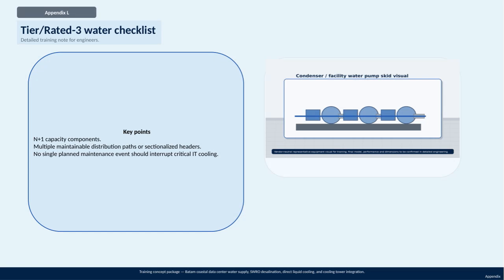Here in Appendix L, we focus on the Tier 3 water checklist, which serves as a detailed training guide for engineers. This training concept package is specifically designed around the Batam Coastal Data Center's water supply system. It covers crucial elements such as SWRO desalination, direct liquid cooling, and the integration of cooling towers. The key points to understand include the use of N+1 capacity components, ensuring redundancy and reliability. Additionally, there should be multiple maintainable distribution paths or sectionalized headers, allowing for flexible and reliable water flow management. Most importantly, no single planned maintenance activity should ever disrupt critical IT cooling functions. This ensures continuous operation and protects the data center's uptime.